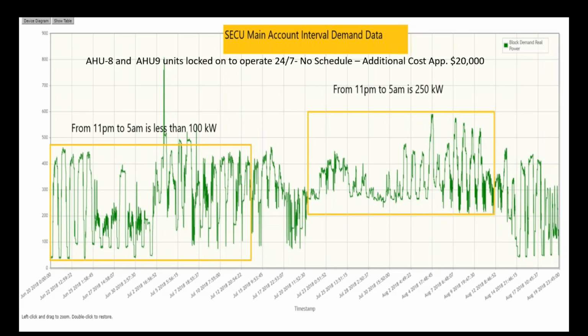Here's an example where a small change took place where someone inadvertently decided to turn an air handler on and defeat the automation, basically locking it on. Our energy office, through good metering and good analysis, noticed within a few weeks a significant increase in the nighttime usage in this particular building, which is one of our sports arenas. It resulted in over $20,000 just because somebody locked on an air handler and forgot to take the lock off in the automation system. It shouldn't have been done, it was a mistake. Most of the time when that's done, it's not necessary, but these are the kinds of things that happen.